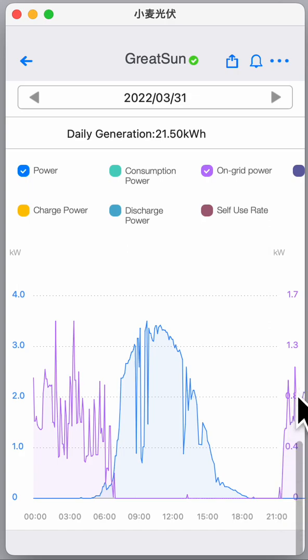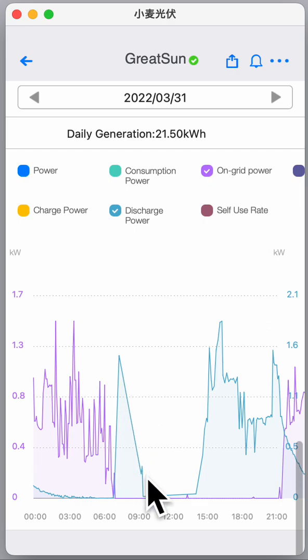In the night when Veco kicks in — unfortunately I can only overlay two charts — this gap is filled by the battery. I have to switch and use the discharge power from the battery. This is a graphical artefact, but you see how the battery charged the day before comes in until it's empty. Then the battery starts taking over — discharging up to 2 kilowatts — delivering enough power to run the air cons, and only when it's empty does the inverter automatically switch to grid power from Veco.